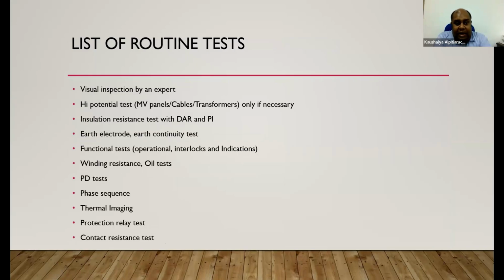This is for routine installation, same thing, but except a few that you don't need to do. And high potential test on cables is not recommended frequently, especially DC high pot tests. You can do it as a commissioning test, but not as a routine test.